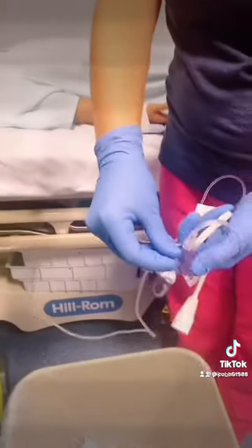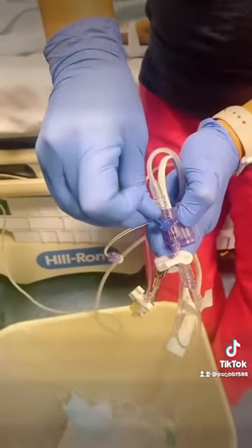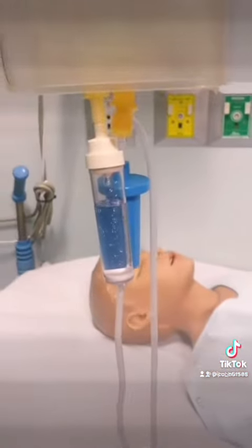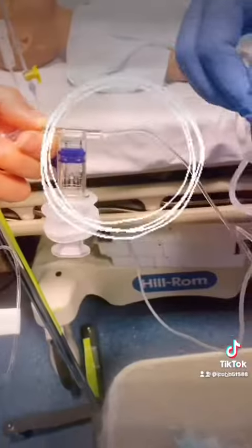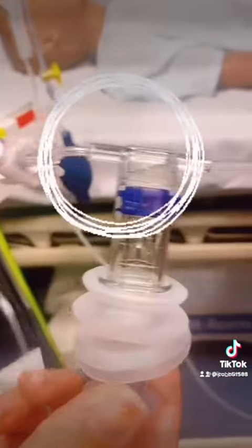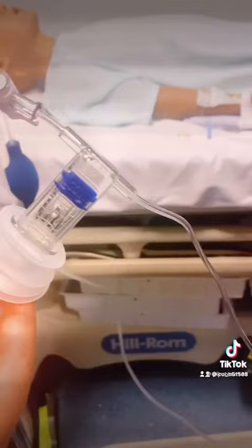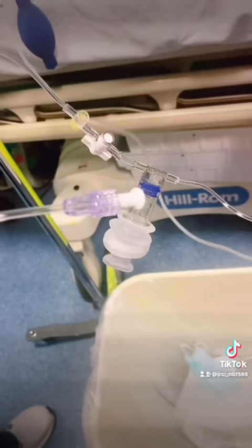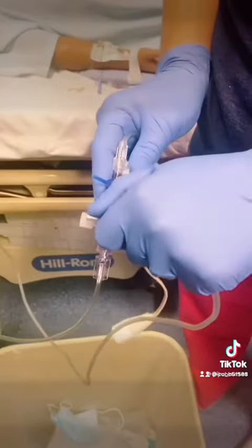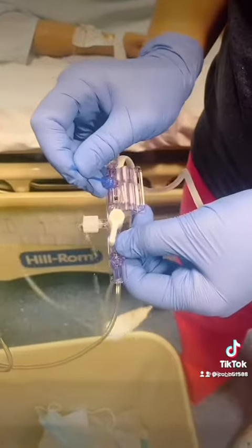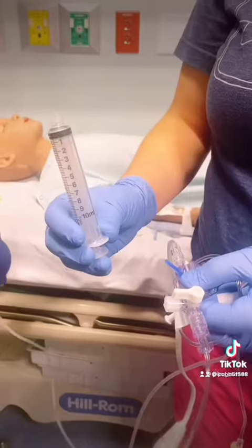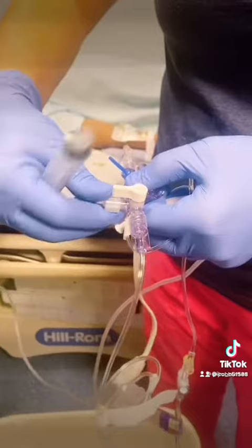The trick is you have to pull the blue pigtail, and once you do that, you will then start to have flow. Here we have bubbles, yay, and the line's getting primed. Make sure the reservoir is also primed and there's no air in it. In order to do that, it's helpful to turn it to the side like this and prime all the way through. Then you'll want to prime through your port by turning off to the patient, pulling the pigtail, and then opening back up. The only thing you'll need to add is a 10 cc syringe.